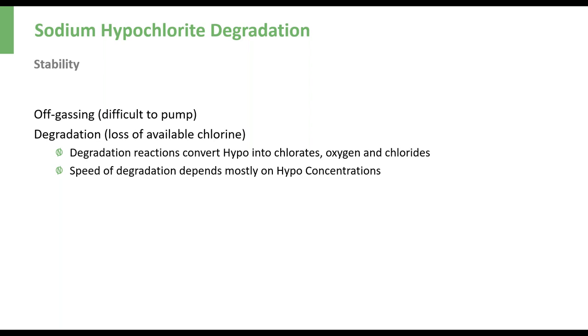process. Now, the main issue you run into is degradation. And what degradation is, basically, is the loss of available chlorine. So that is what you paid for. It goes down. Okay, degradation, two things happen. The degradation reacts and converts the hypo that you purchase into chlorates, oxygen, and chlorides. So that is it attacking itself.